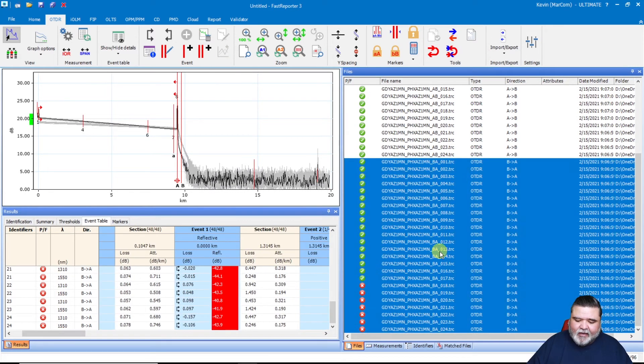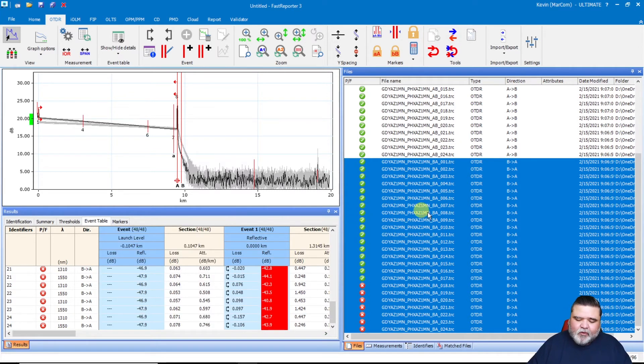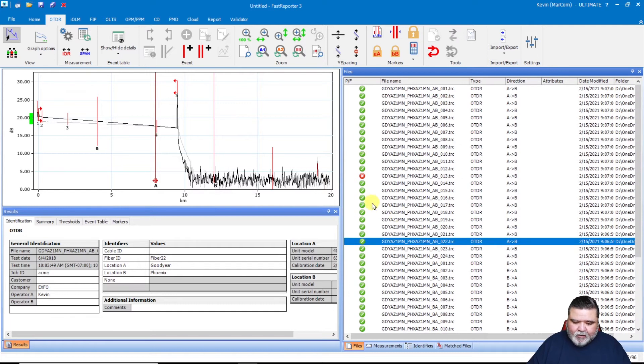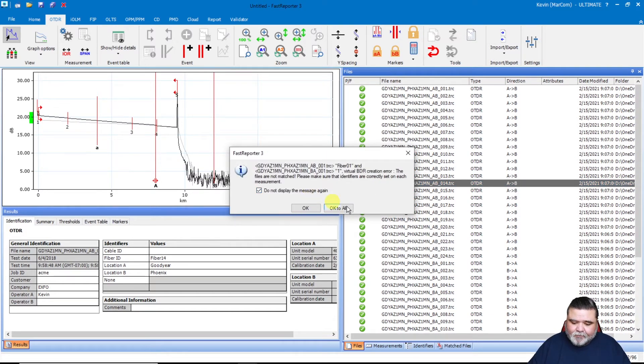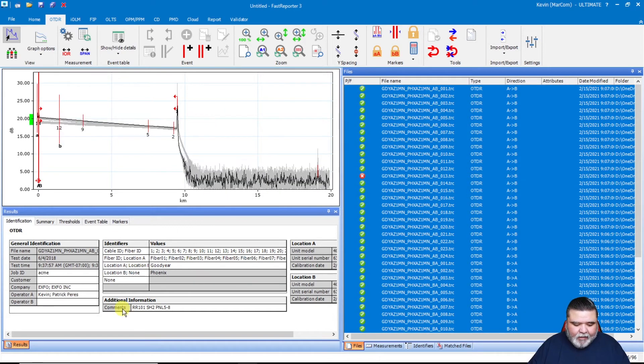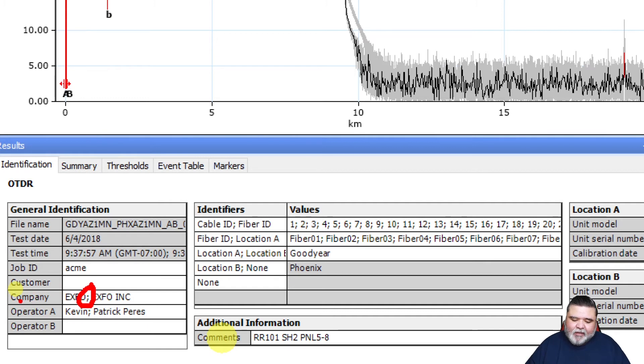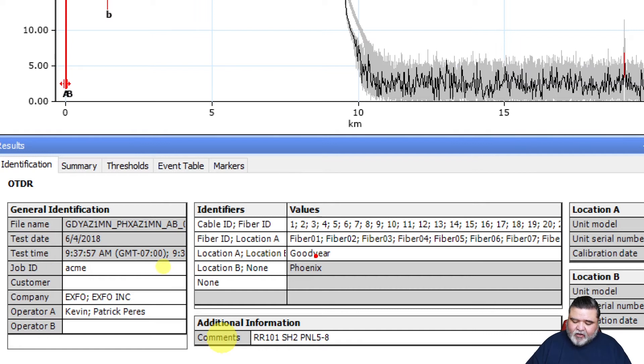Now that we have all this test data looked at and validated — we do have some fails, but for demo purposes that's fine — I'm going to make sure I have all of my identification right. I'll hit Control-A to highlight all the files and look at the identifiers that were populated. Anytime you see a semicolon it's an indication that this value has different values for different traces. Some say EXFO uppercase and some say EXFO Inc. Some locations say Goodyear, some say Phoenix, some aren't even set. The fiber IDs on one side save as one format and on the other differently — we have a bit of a mess here.